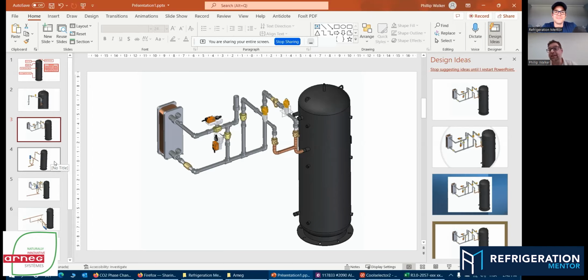We're doing radiant floor heating to even plant growth, right, with glycol loops and plate heat exchangers. A lot of the time, that returning temperature from the glycol loop maybe is being used for an air conditioning circuit or plants or LED cooling, right? It's typically after it's heated, it's coming back at a temperature still lower than the gas cooler. Well, we can take that temperature, say if it's 85 degrees, and heat it and provide some cooling, because maybe my outlet on my gas cooler, it's a dry gas cooler at that moment, is 95 to 98 degrees. My glycol's coming out at 85, so we can knock off a few degrees from the gas cooler outlet.